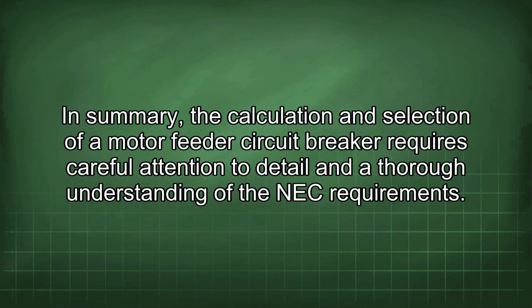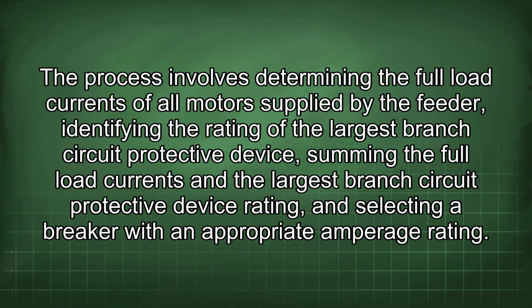In summary, the calculation and selection of a motor feeder circuit breaker requires careful attention to detail and a thorough understanding of the NEC requirements. The process involves determining the full load currents of all motors supplied by the feeder, identifying the rating of the largest branch circuit protective device, summing the full load currents and the largest branch circuit protective device rating, and selecting a breaker with an appropriate amperage rating.